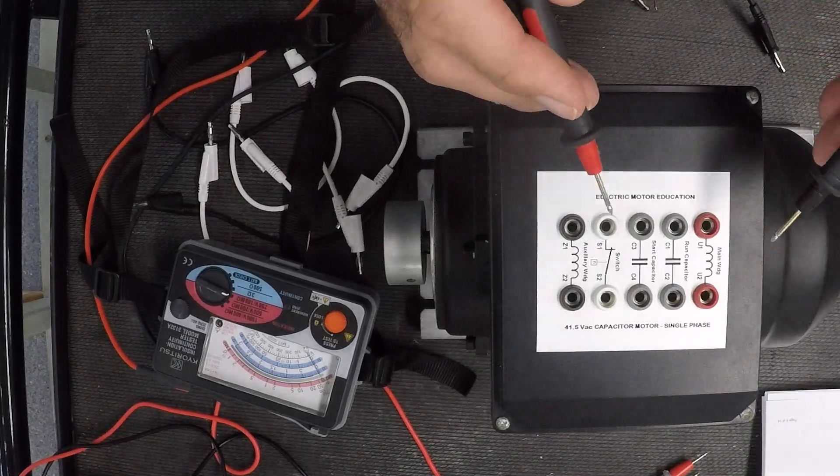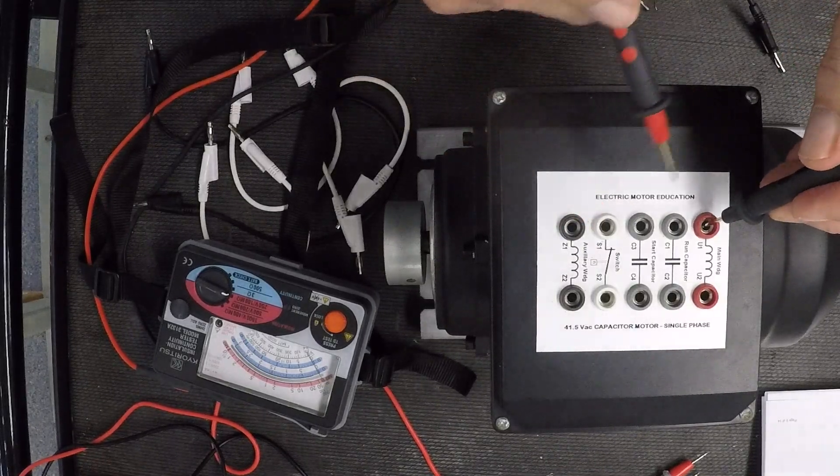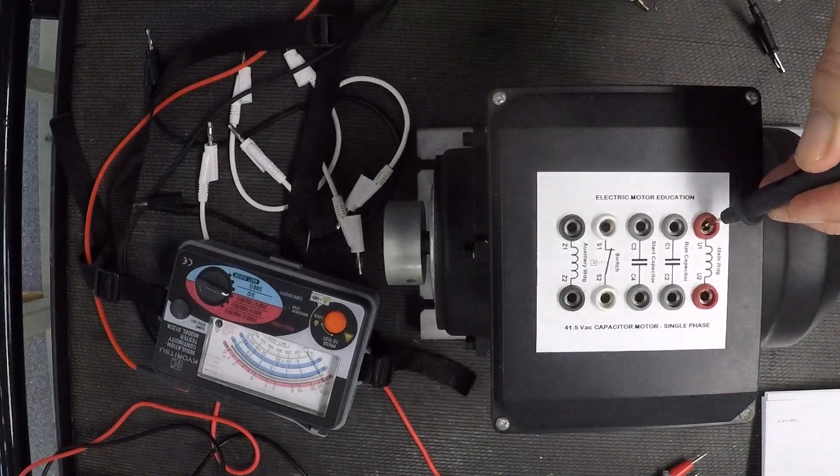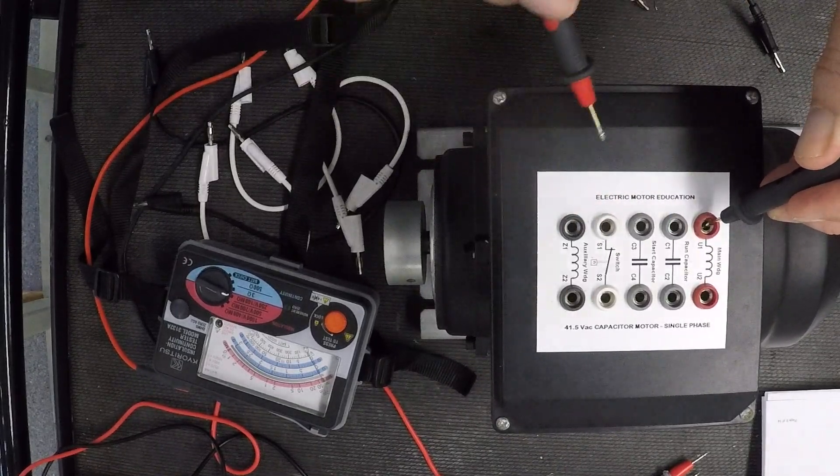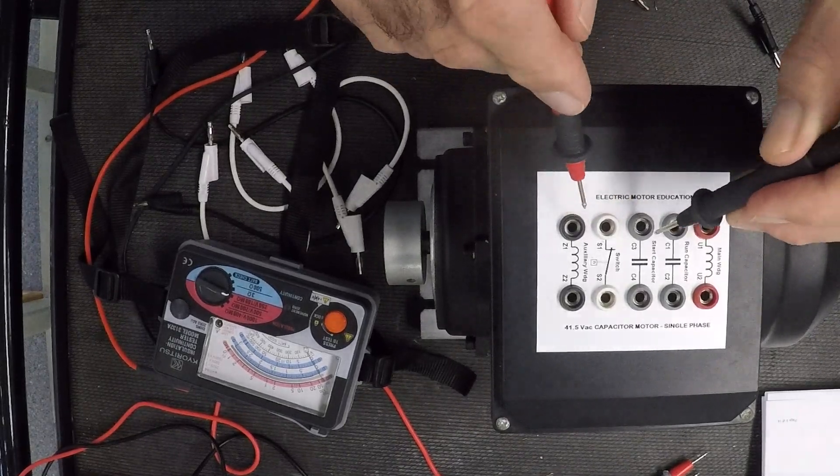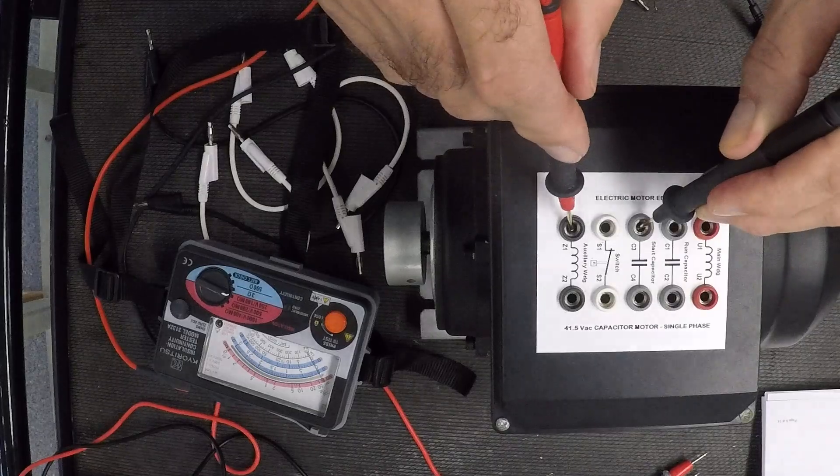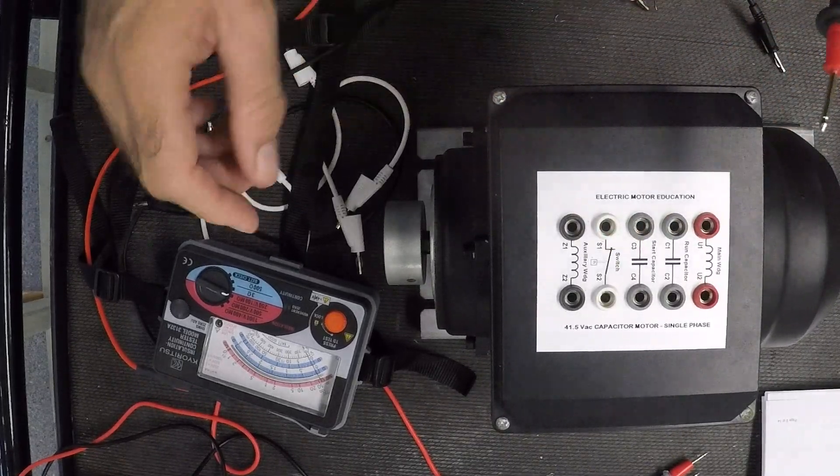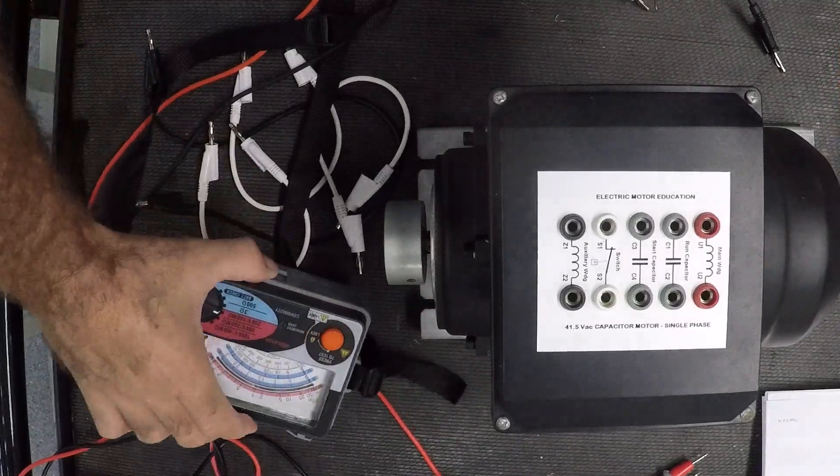So I'll just go to one point and check all my other points just to make sure internally there's no fault. I'll go to the next one—check, check, check, nothing. Check again, again, touch the leads again. I now know that this motor is fit for testing or for connecting.